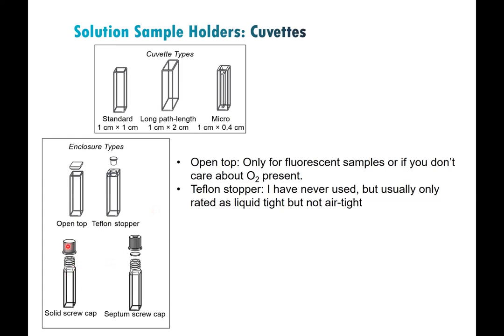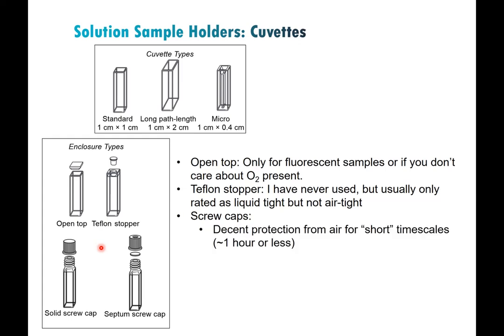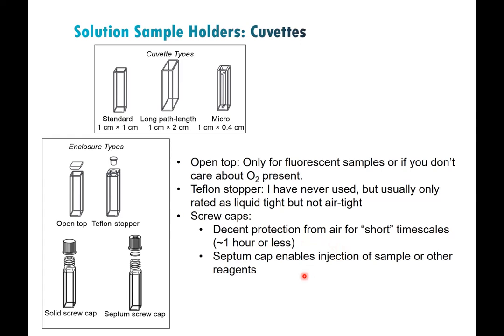Since we mostly work with phosphorescent compounds, we use airtight cuvettes. Screw caps offer pretty decent protection from air for short periods — an hour or less is probably the time scale you're thinking about, though it varies by sample. The advantage of the septum cap, which we often use, is that you can inject the sample for a serial dilution, or inject other things like air or reagents if you're doing a quenching experiment where you want to vary concentration as you're doing the measurement.